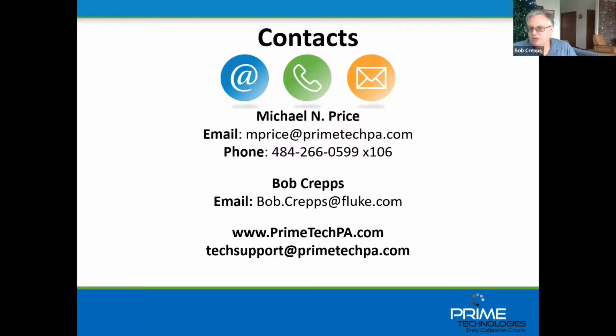But if you want to do full HART, let's say commissioning, for example, then I would recommend pairing up that 753 with a Fluke 154 communicator, which supports the entire DD library. And I'm not trying to sell anything, but you do get free quarterly updates with the Fluke 154. So that'd be a great add-on to the 753 if you don't want to do a direct HART calibration like we just did with the 754.